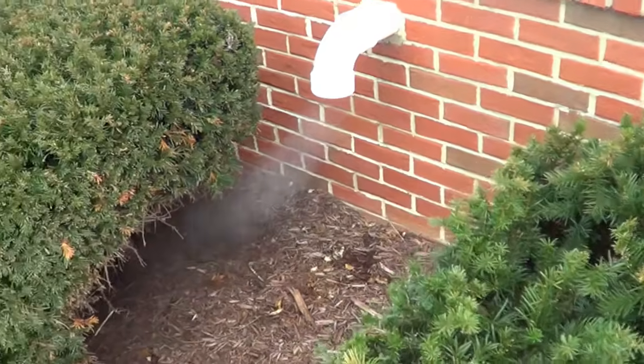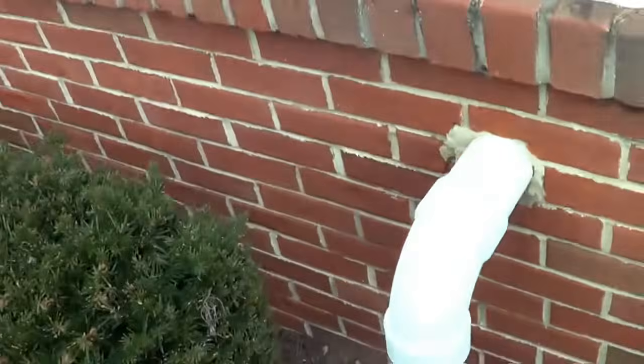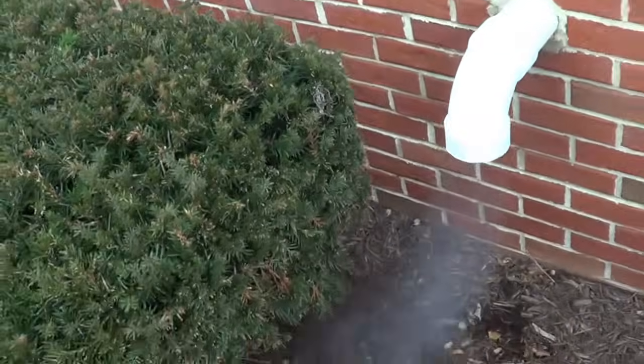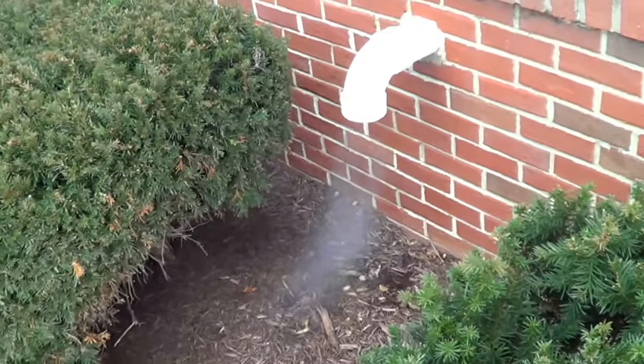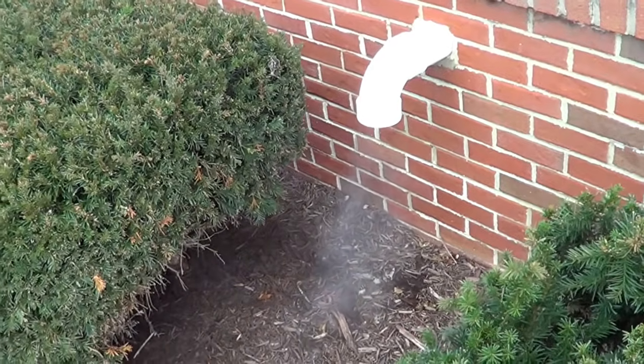You can see the flame is not touching the walls. It's getting sucked in completely. After cleaning the heat exchanger, I got a nice clean exhaust now. You can barely smell any odor at all, just very slight odor, and that's complete combustion.